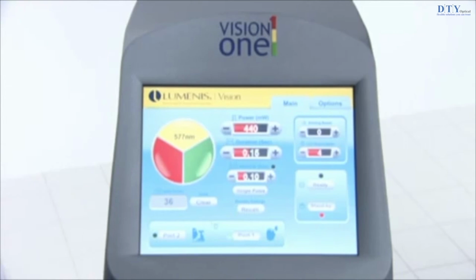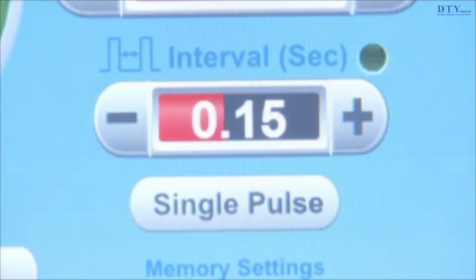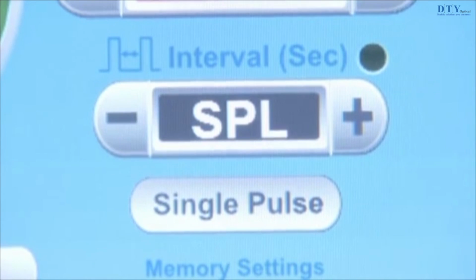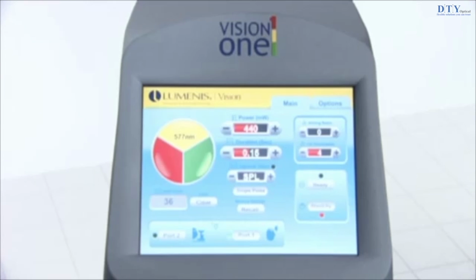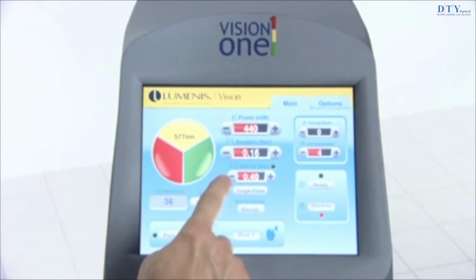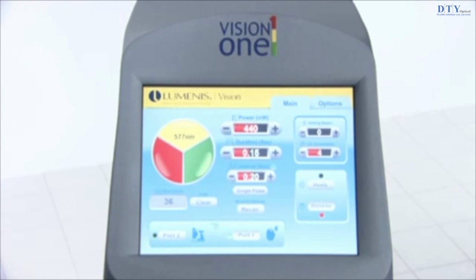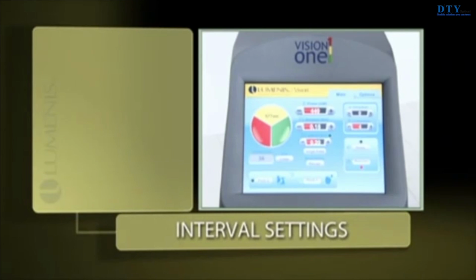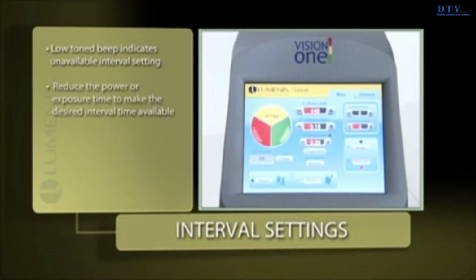The treatment interval is the time in between laser exposures. Single and repeat exposure modes are available. In single exposure mode, the laser delivers a single exposure each time you depress the foot switch. In repeat exposure mode, the laser delivers repeat exposures at a specified interval until you release the foot switch. Not all interval settings are available at the higher power and exposure time settings. If you attempt to select an interval that is unavailable at the existing power and exposure time settings, the laser emits a low-tone beep to indicate that the selection is not available. You must reduce the power or exposure time setting to make available the desired interval.